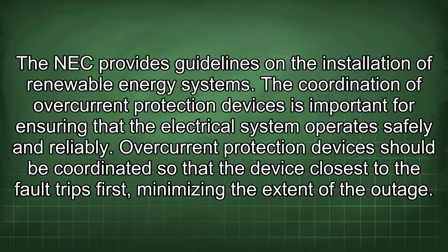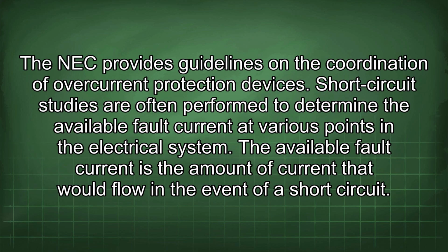The coordination of overcurrent protection devices is important for ensuring that the electrical system operates safely and reliably. Overcurrent protection devices should be coordinated so that the device closest to the fault trips first, minimizing the extent of the outage. The NEC provides guidelines on the coordination of overcurrent protection devices.